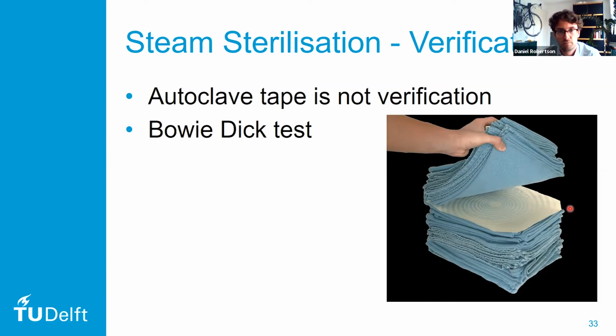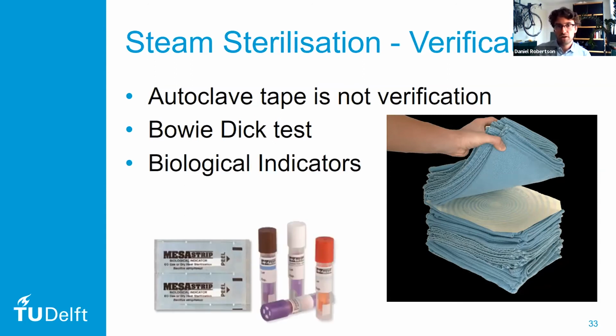What this pack of sheets does is create a challenge for the steam to reach into. So if this sheet is completely changed color, we know that all of the instruments in the autoclave have come into contact with the steam. Now, besides this test, in some parts of the world, biological indicators are always used as a verification.